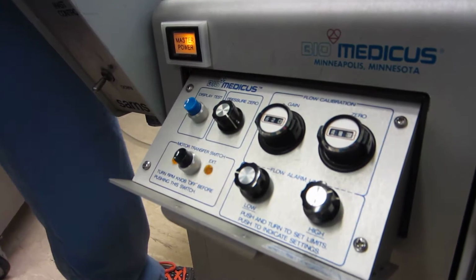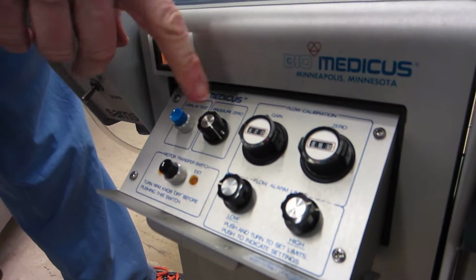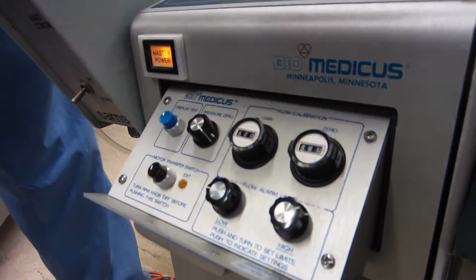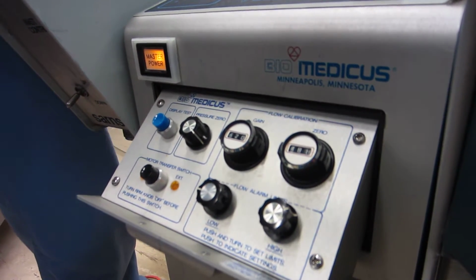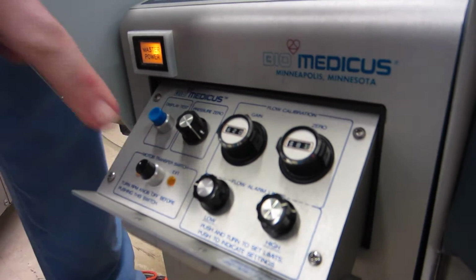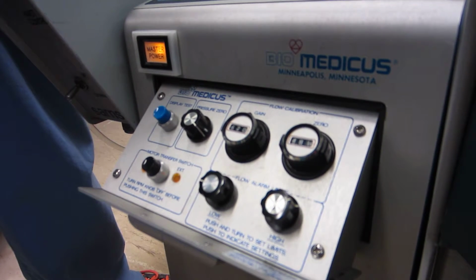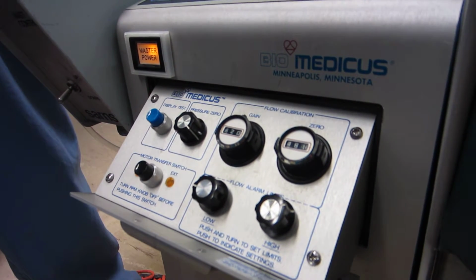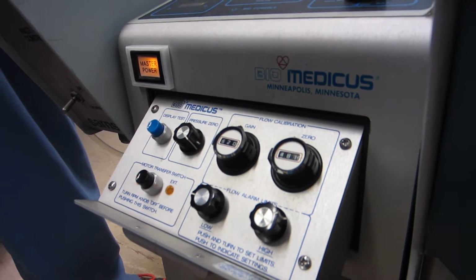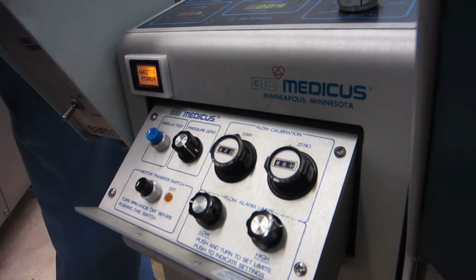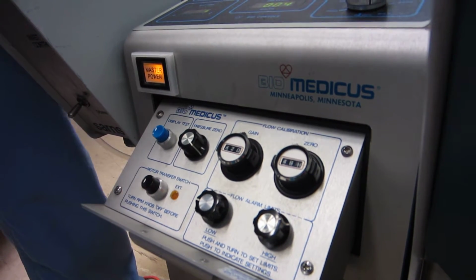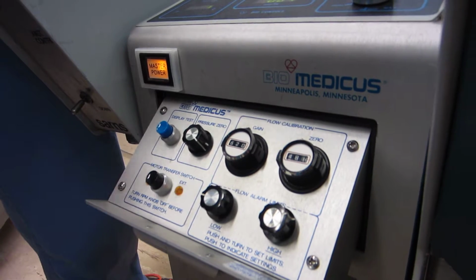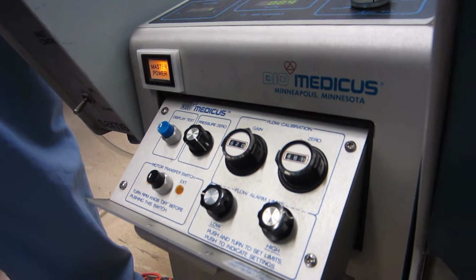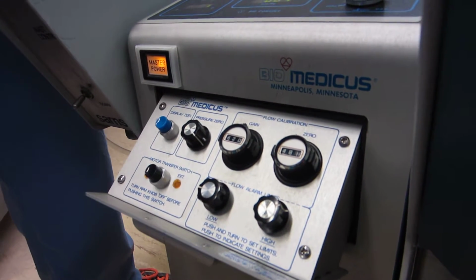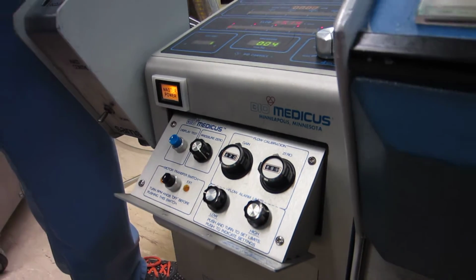Okay, you have a pressure display or a display test for everything. You have a pressure line just like you have on the 550 or the 560. And then internal and external. Who can tell me what that means? That internal head. So if the head is mounted on the pump, it must be on an internal drive. Okay, if the head is mounted on a tether, it must be on an external drive.